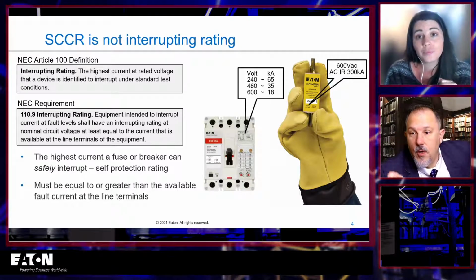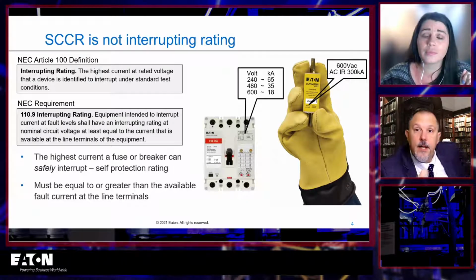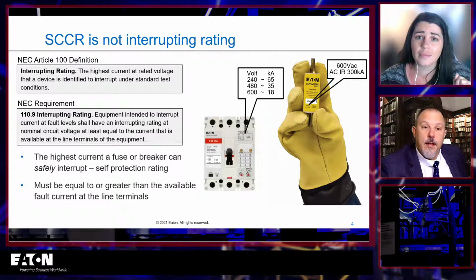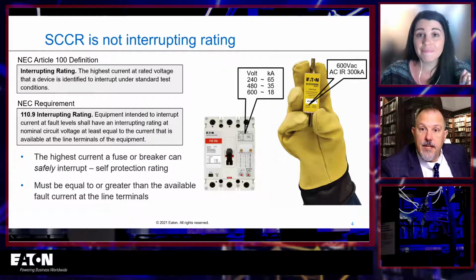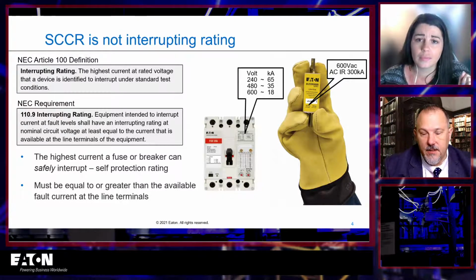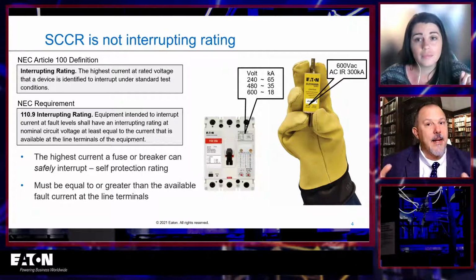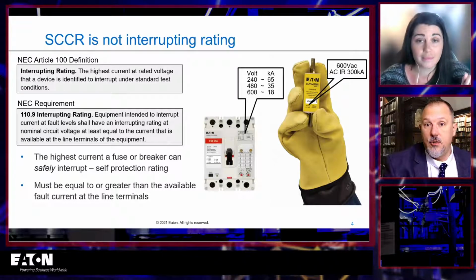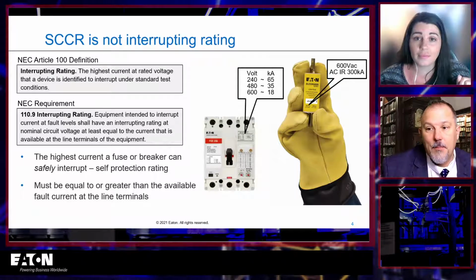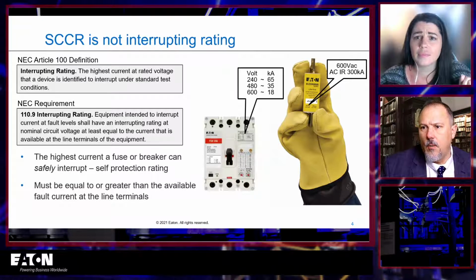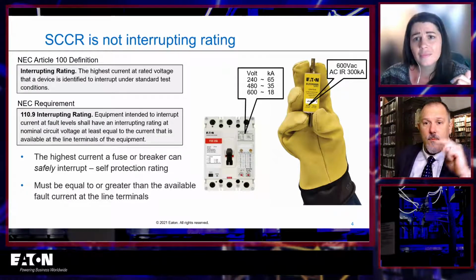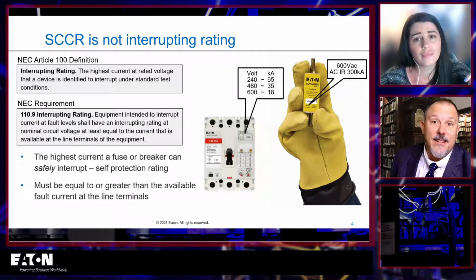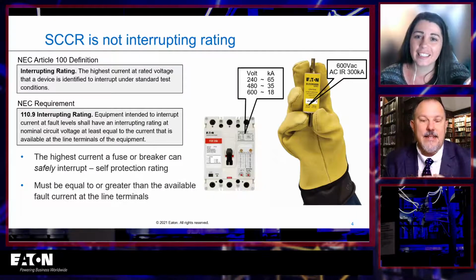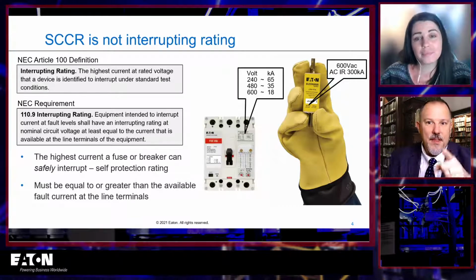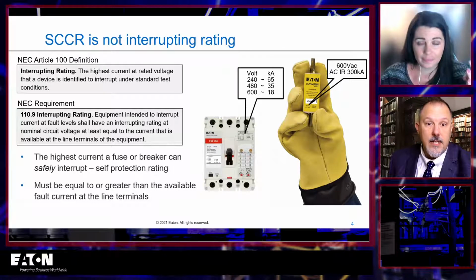And I think too, Christy, Robert from Omaha brought it up about 50, 60 hertz in the interrupting ratings. I know that there are resources to derate the interrupting capabilities when you go to those very high frequencies. If you look at the overcurrent protective devices, they'll have a 50, 60 hertz interrupting rating. But when you start getting outside of that, you really need to consult the manufacturer to say, okay, what is my new rating? So that's another aspect, and he brought something else up as well. He says, "What about ambient temperature impact of this?" And I like the way you described this, and I'm going to steal it from you. That interrupting rating is about the device itself. It's not about anything around it. So when you think about this device, you really have to understand what its capabilities are based upon the environment that it's in, whether frequency and all that good stuff play a role.